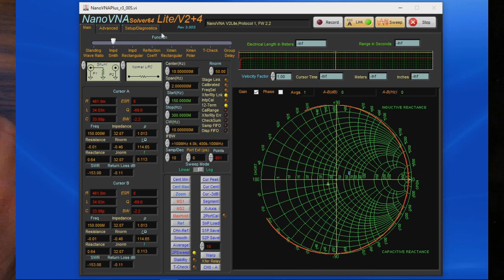In the older software there was an LED that told you the transfer relay was selected. That's been removed. If we select Setup Diagnostics and then the Calibration Terms tab, when we look at the calibration standards, you'll notice a value of 1.0 e to the minus 9.